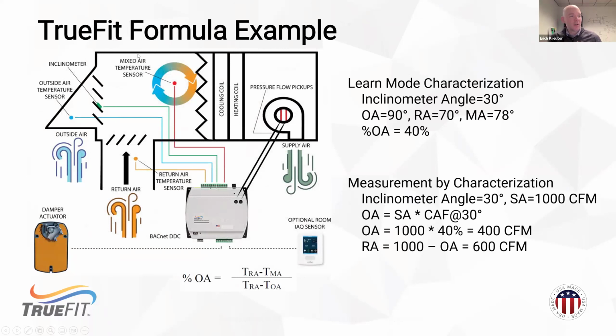So this is a portion of the math that makes it pretty easy to understand. When we're going through learn mode for any given position, here we just chose 30 degrees, but again, it's just a given position in space. If I know all 3 temperatures, we can calculate with that ASHRAE 111 formula what the percentage of OA is. Here, for 90-degree OA, 70-degree return, and a mixed air of 78, we know there's 40% OA present in the supply airstream.